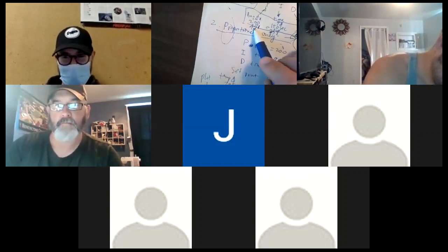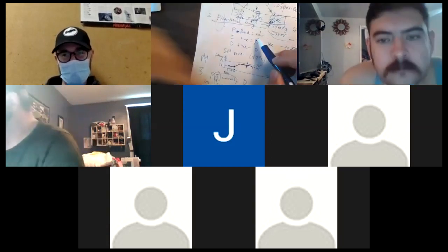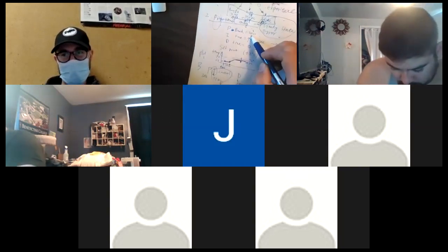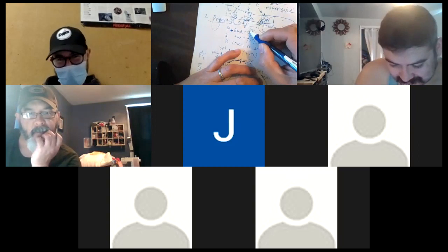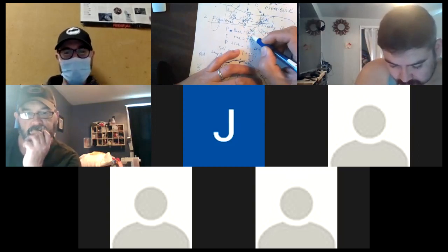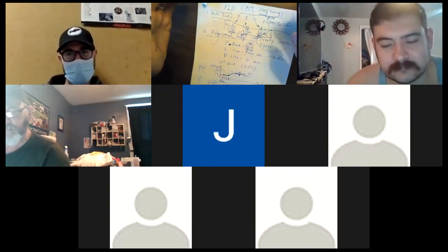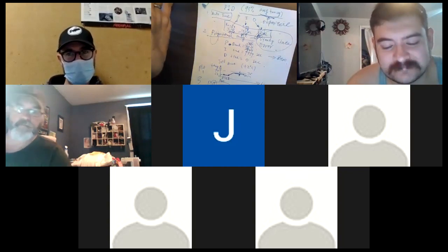So if Joe is working on step number 2, Joe will put 450 here, 470 here instead of 200. Depending on the result of your auto tune, you will change numbers here. So for Tim, you will put 150 here. For Joe, it will be 550 here, 450 here. So you do your test based on your results. The auto-tune result is based on a lot of factors, like I said, the size of your incubator, the power of your heater. Okay, anybody else have comments?